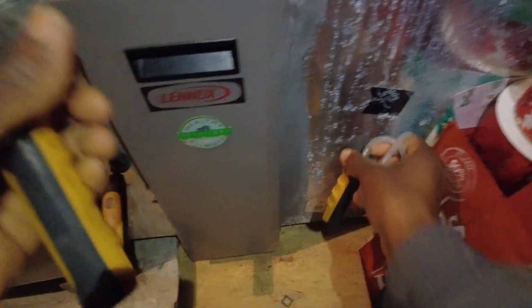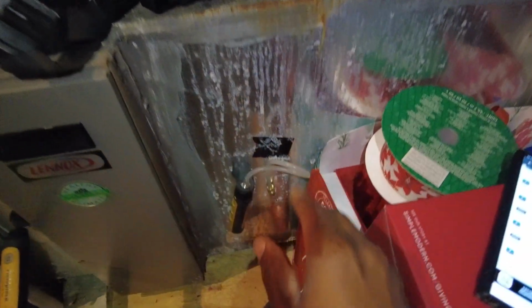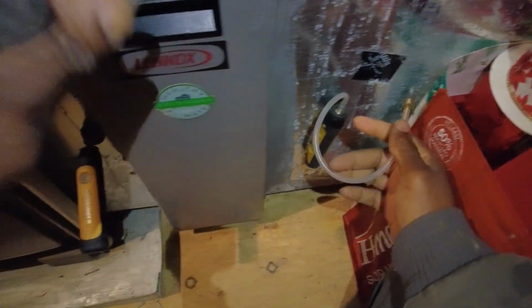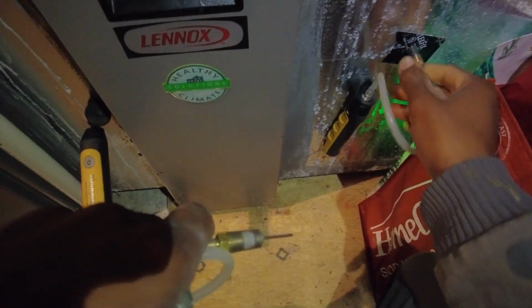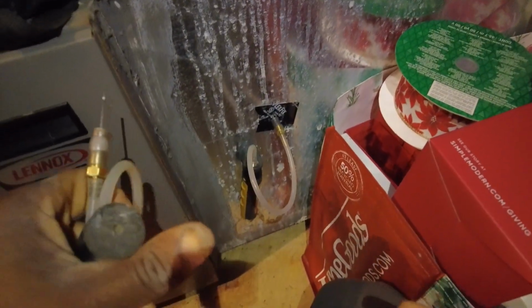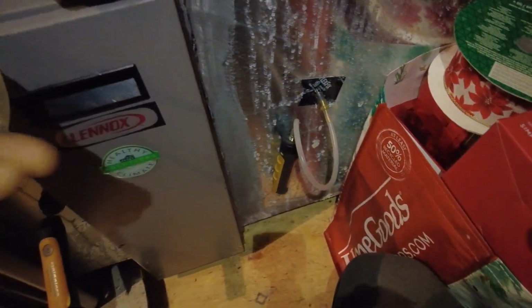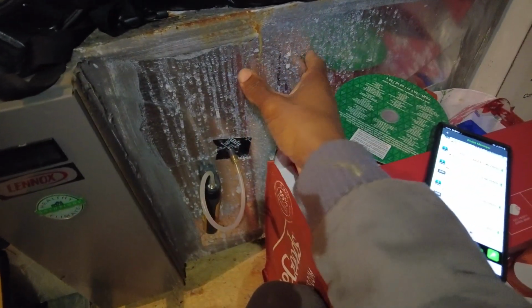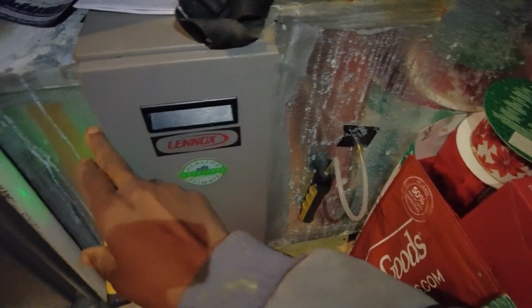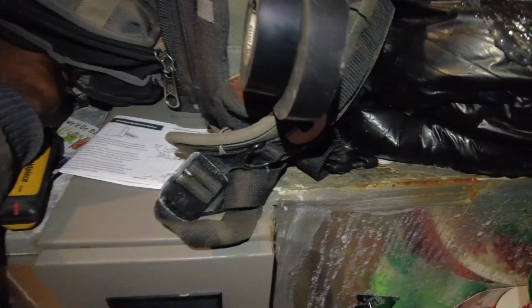Okay, so now I'm going to check the static pressure before this filter media cabinet. This is basically going to show me where a lot of my bottleneck is, which I know is going to be this filter media cabinet. But I want to see how much the return and all these ducts themselves contribute, because what we may be able to do is add another cabinet to this box, with one coming off the side and one coming off the top, and connect the plenum directly to the side of the furnace. That'll free up our return static.